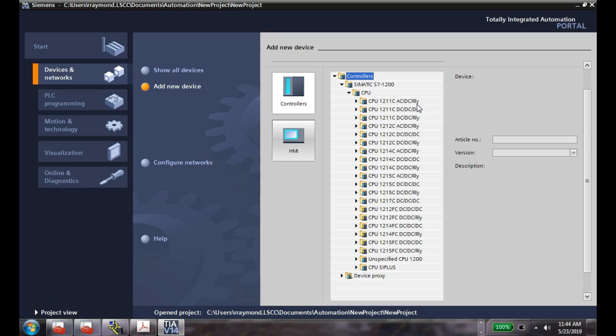Everybody know? It doesn't care if it's AC, it doesn't care if it's DC, it doesn't care if it's 120 volts, it doesn't care if it's 15 volts. So it's more flexible on what type of output devices you're going to run, right? If you've got a DC output, you get what DC it is, and the predominant value, guys, is 24 volts in PLC. So we put 24 volts in here on our inputs, right? You understand it's a DC input, right?